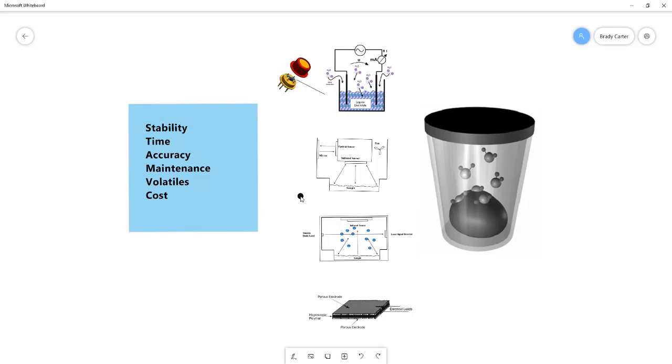To make sure that they're meeting those specifications, you have to actually do some verification, and that comes to maintenance. How frequently does that verification need to be done? For instance, on the dew point sensor, it will give very accurate results, but you do have to make sure that nothing's happened to affect that. And thinking back to the stability, again, if there's any kind of contamination on the mirror or the sensor, it will affect the readings. So in order to achieve the high level of accuracy, you have to verify it and you have to clean it very frequently.